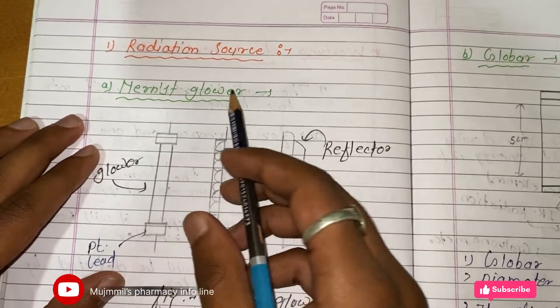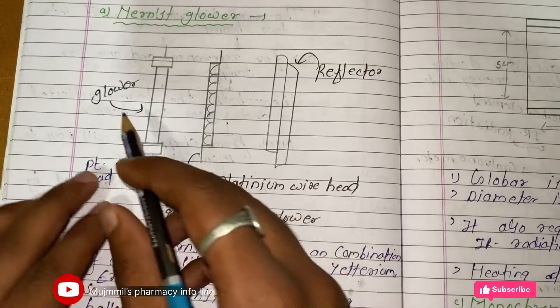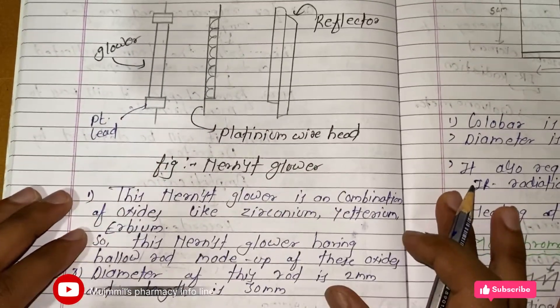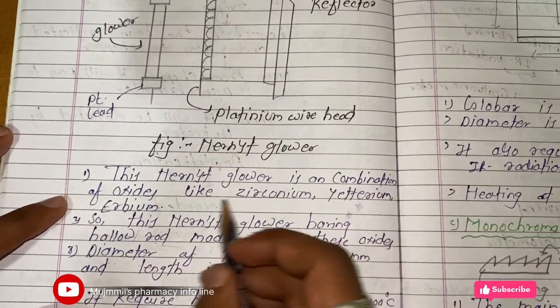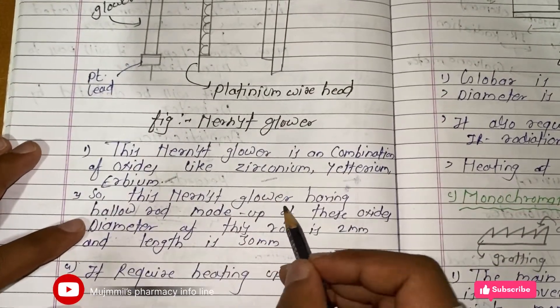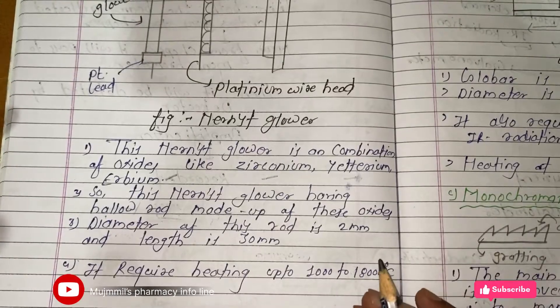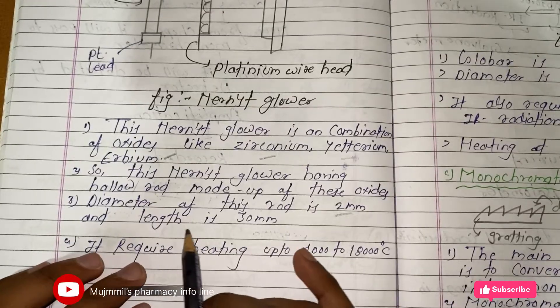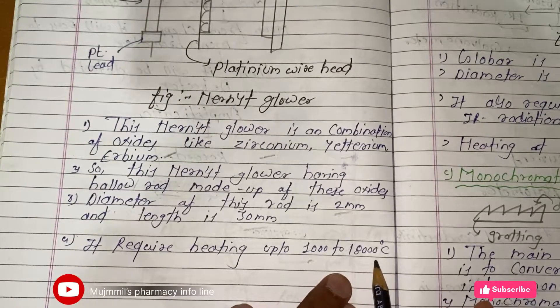Let's see the radiation sources used in IR spectroscopy. The first is the Nernst glower. It has a reflector, a platinum wire head, and a glower with a platinum head. The Nernst glower is a combination of oxides such as zirconium, yttrium, or erbium. It has a hollow rod made of these oxides with a diameter of 2 mm and length of 30 mm, and it requires heating up to 1,000 to 1,800 degrees Celsius to produce IR radiation.